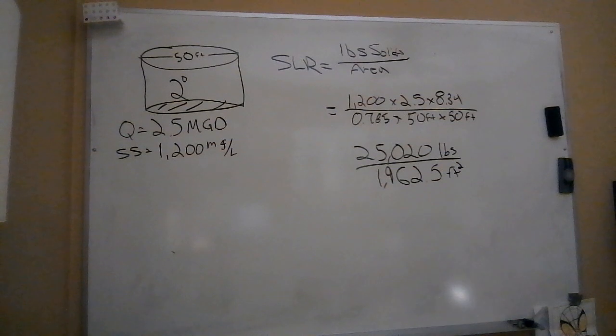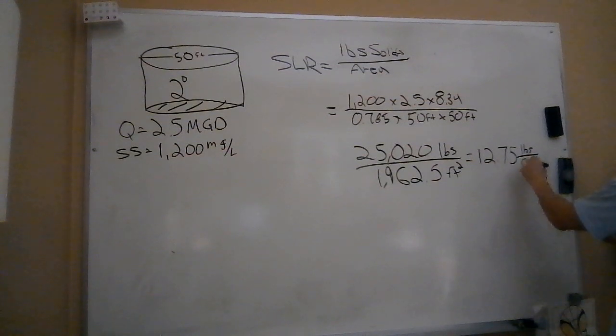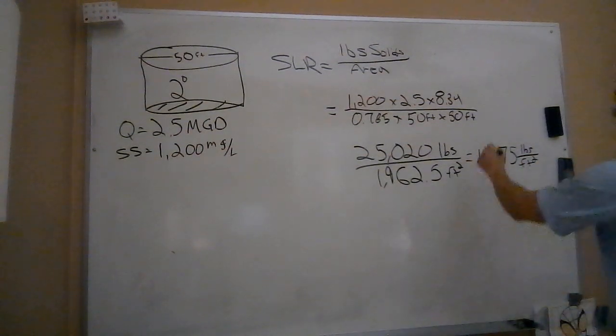1962.5, and this is going to be square feet - an area. Feet times feet gives me square feet. Now I'm just going to divide those two out: 25,020 divided by 1962.5, and that's going to get me to 12.75 pounds of solids per square foot of clarifier. That is my solids loading rate.